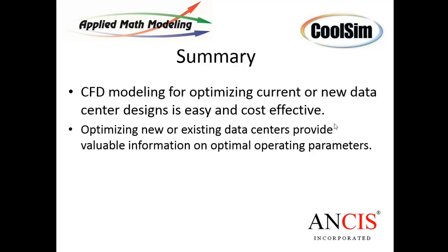Question here about modeling opti-cool systems, unrelated to our webinar, rear door heat exchangers. Yes, we can model rear door heat exchangers, and that's not a problem. You treat them very much like you would an in-row cooling unit, but it's sitting behind instead of beside, and yeah, you can model those.